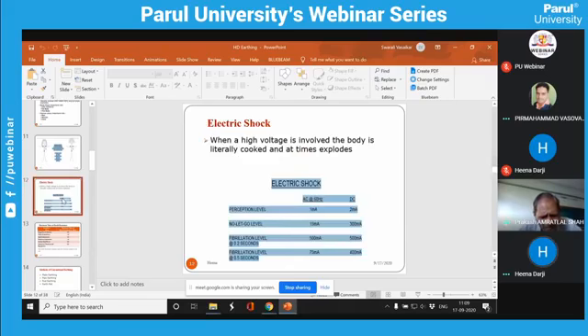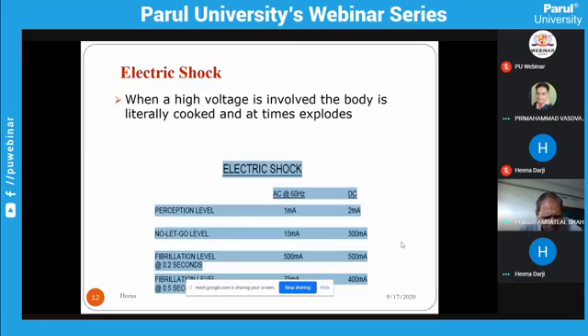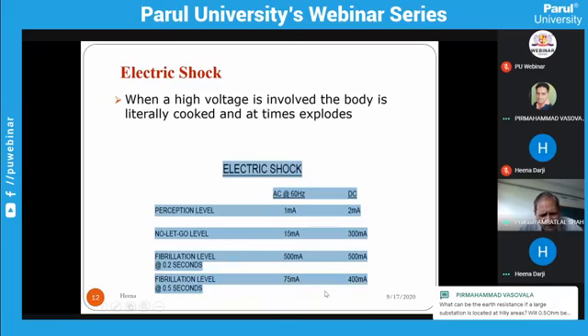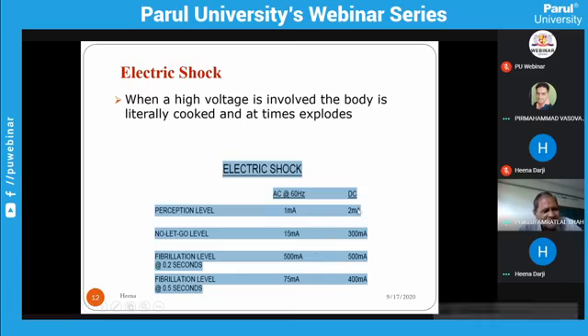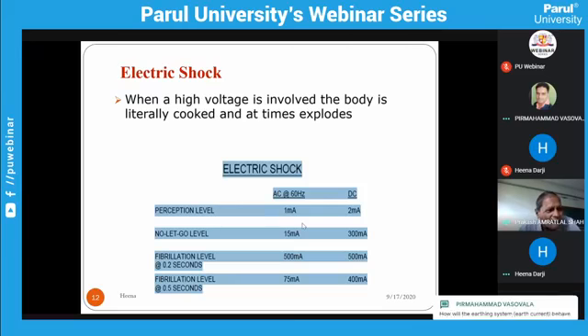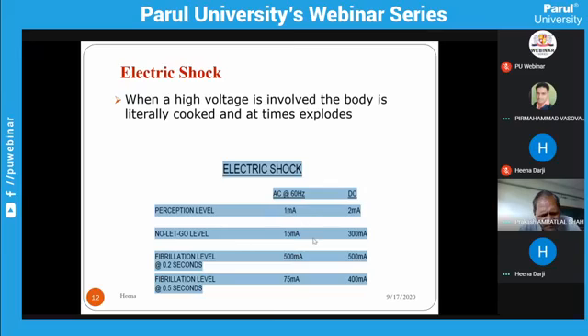Here is the chart where you can see that the current is different for perception, fibrillation and other thresholds. In AC, what is happening? When you get the shock, the sinusoidal wave is there, so in 1 second you will get the shock on and off 50 times. You get the shock, then you leave the shock. Therefore, the currents are different. That is the main purpose. In DC, once you get the shock, you will get a continuous flow of current.